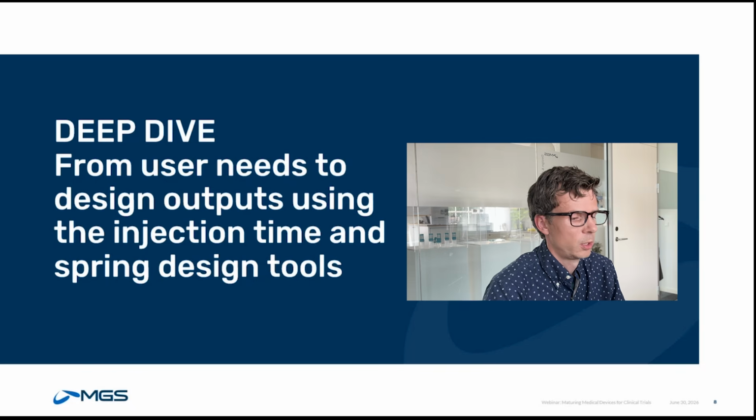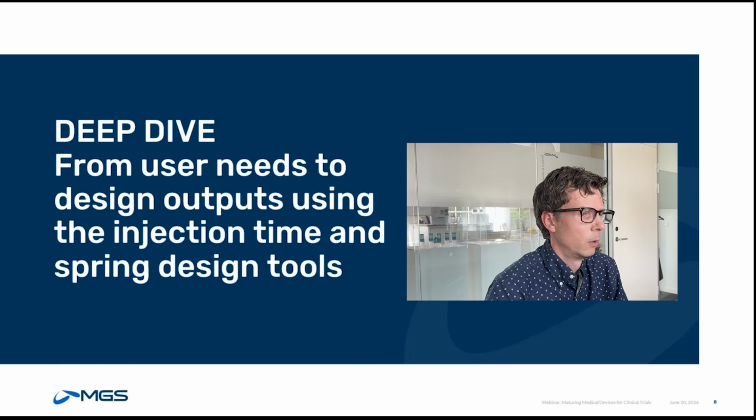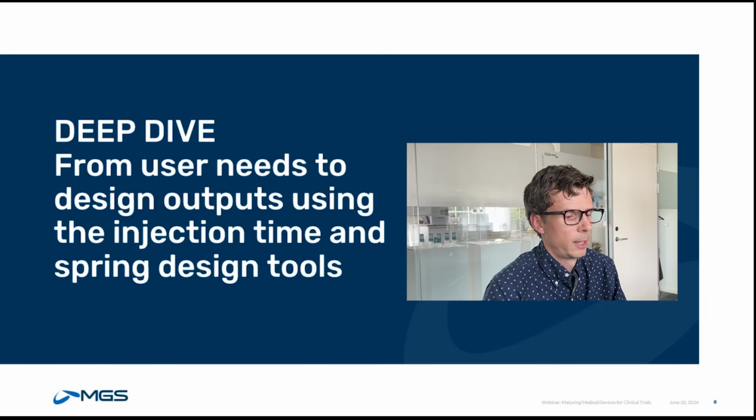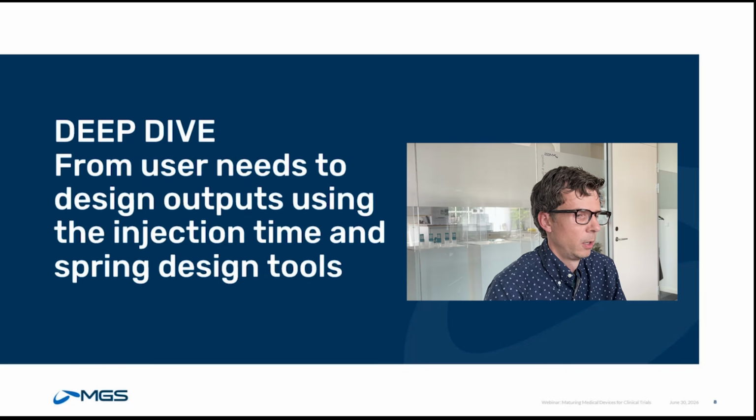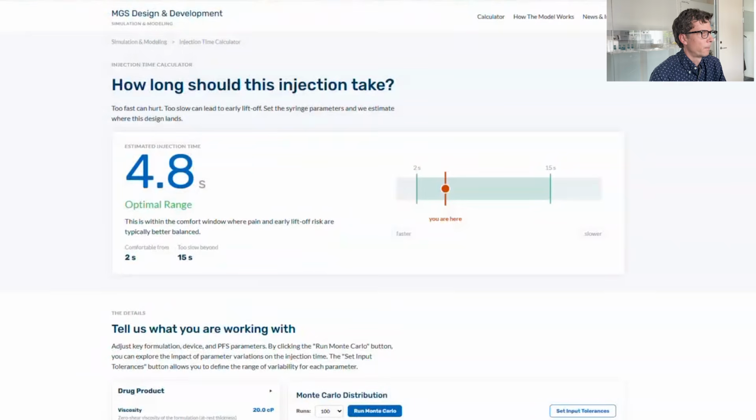So if the injection time is too long, the user might lift the device. But if it's on the other hand too short, it might give a poor injection control and discomfort that could also lead to the user lifting the device. So the injection time is not just a performance driver, it's a key risk driver. But let's go into the injection time.